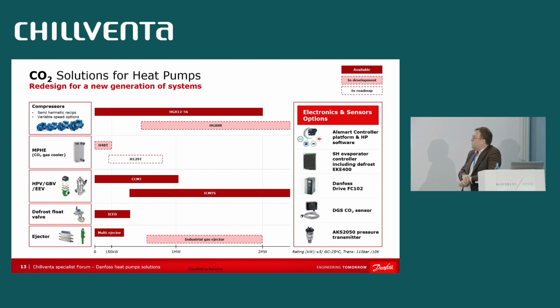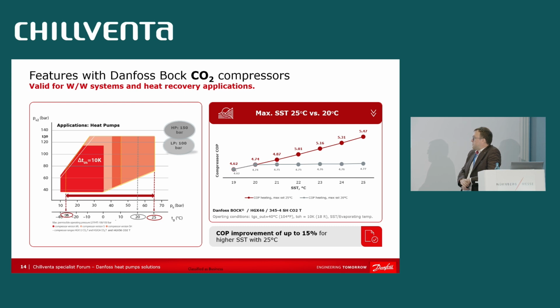And for what concerns the compressors, what we've been working on a lot lately for CO2 application at Danfoss is, as much as possible, we do think that CO2 can be used a lot for water-to-water application, especially in a heat recovery mode. And we try to operate at as high an evaporating temperature as possible. So the Bock compressors are qualified up to 25 degrees. What it means when you are producing water at 80 degrees, just such as in this case, and you have a return temperature at 40, we are still able to operate, especially during summer, at a higher evaporating temperature, and then you are performing quite well because you are not limited to 20 SST. You are operating at 25 SST, and this is giving quite a nice improvement in performance. This is something that we focused a lot on. This is a special motor that has been developed by the Bock team in order to target this segment and this application for heat pumps.